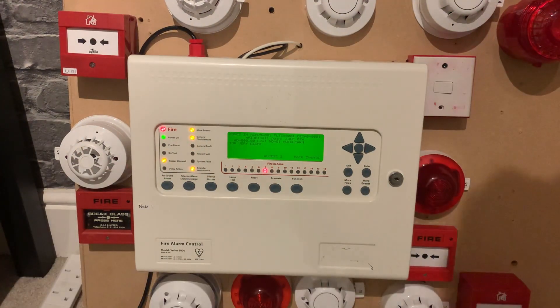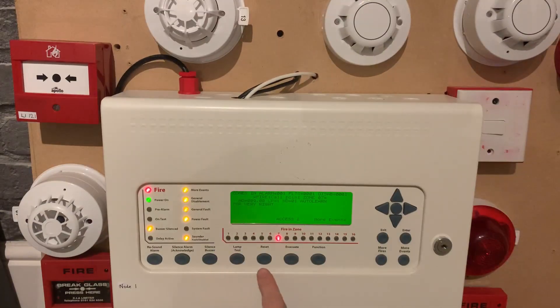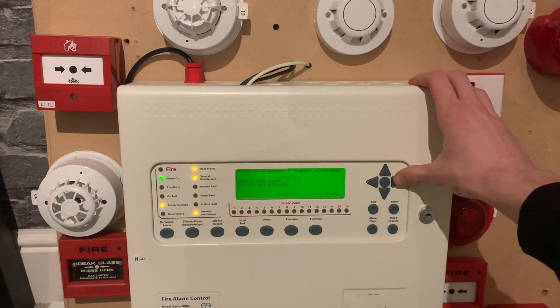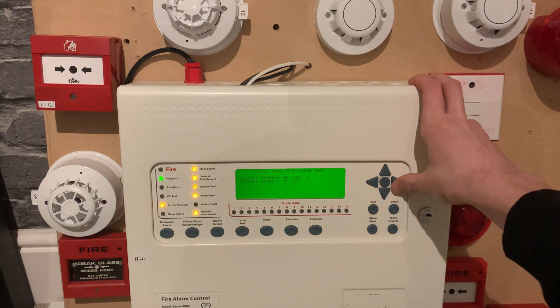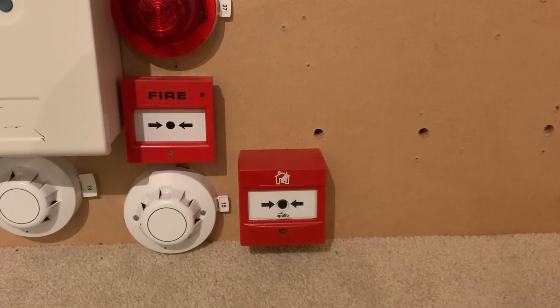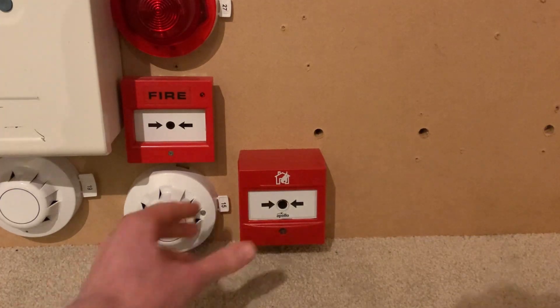Let's now give the intelligent call point a test. I did say we're going to disable the integrated base sounders at the panel. You can see the beacon stutters for a bit — it does that every time I reset the panel, which is weird. We'll disable address one and address three. Here's the intelligent call point — one of my favorite call points, love how it twists, definitely one of my favorites. We'll just give it a press.